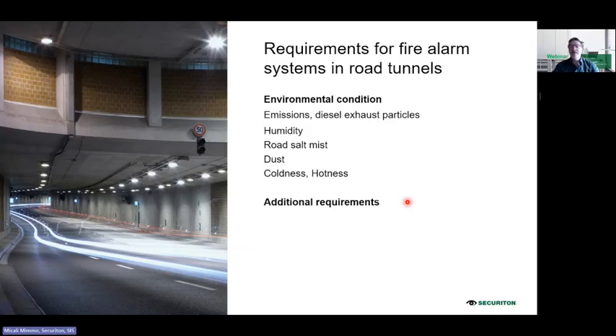Then there are some additional requirements, like system integration. It's important that the system can be integrated. Normally every tunnel has a SCADA system. It's a supervision system where they control all the electrical and the mechanical equipment. Therefore, it must be easy to integrate. Then also the planning, the installation and commissioning must of course be easy. Usually the fire detection system is one of the last systems that you install in the tunnel when everything is finished. So the installation may be very fast, and you also need to commission the system in a short time.